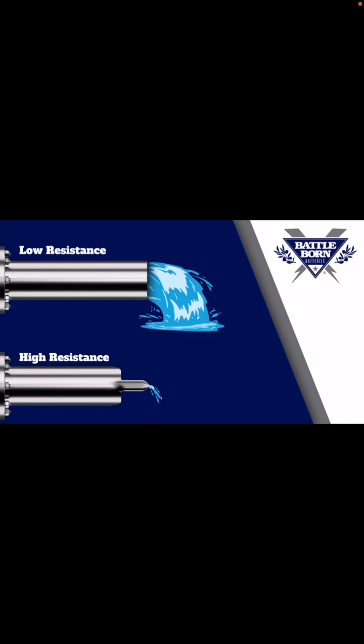So you go to the panel and you check from your hot coming out of your breaker to your neutral bar. So you put one lead on your hot wire coming out. Let's just say it's 120. And you put your other lead on your neutral and you're getting 120 volts across. But then let's say you press on the breaker and you kind of just move it, or you grab the wire and you manually shake it or move it, pull on it. And all of a sudden you see your voltage drop down. Maybe it goes to like 73 volts or it just disappears on your meter. That's an example of resistance.